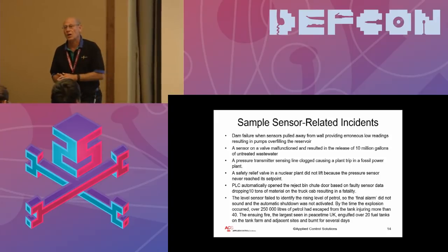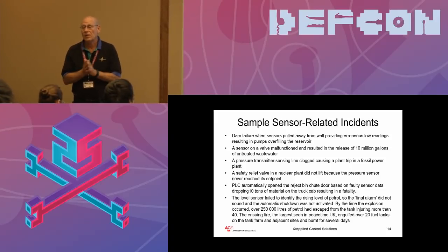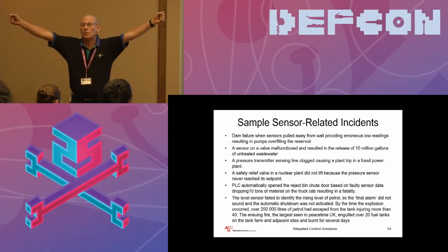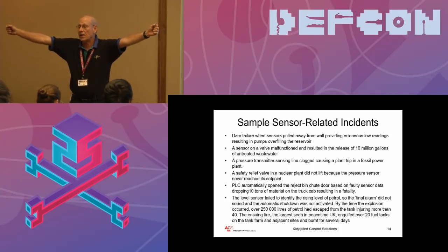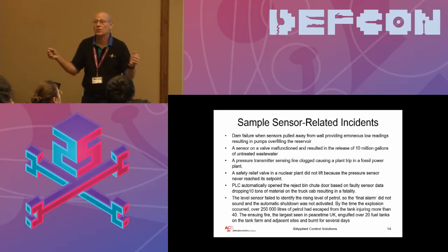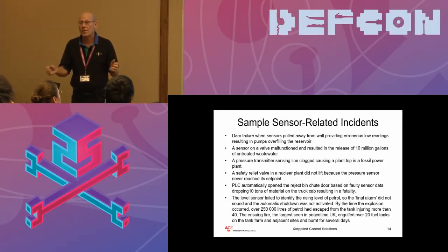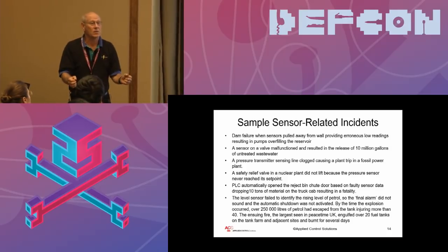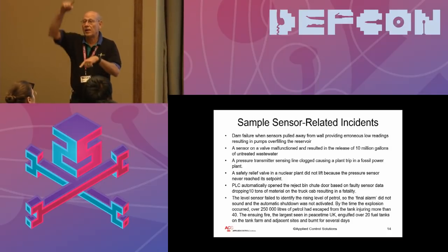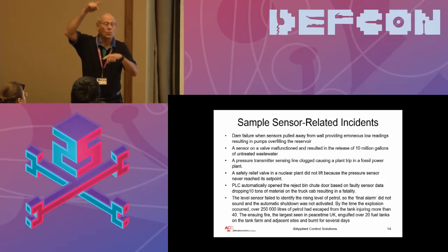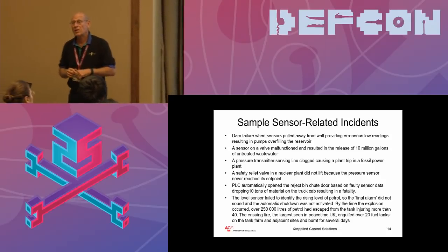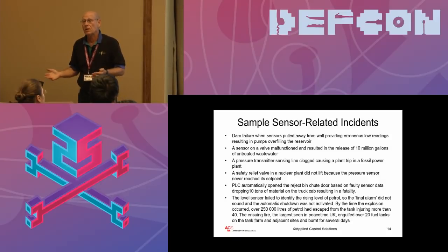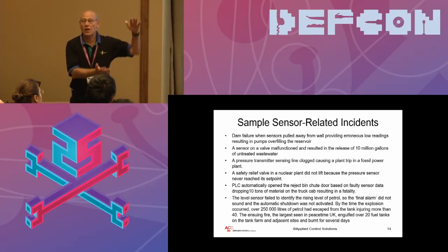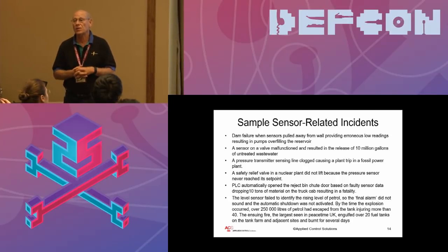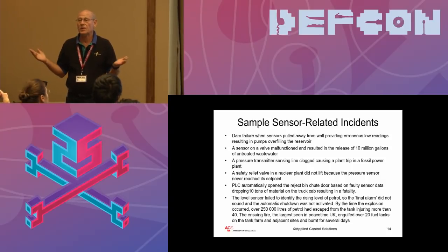What happened there, that's a dam in Missouri. It basically failed about 5 or 6 years ago. It had a couple of level sensors attached to the wall of the dam. The tie-downs broke, so the sensors came out from the wall, and when they did, the level readings changed, because you measure level by elevation head, by height. Well, the height changed, so the SCADA system took the data as real, it had no reason not to. When it said the level was low, it turned the pumps on until the reservoir overfilled and the earthen dam collapsed.